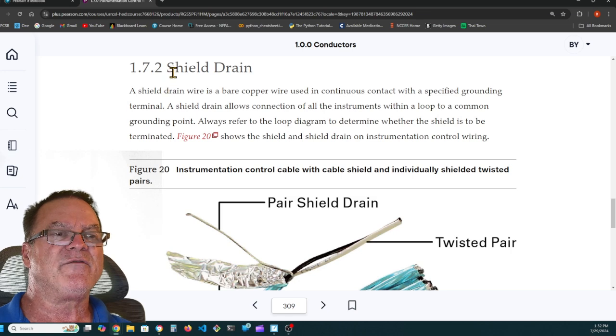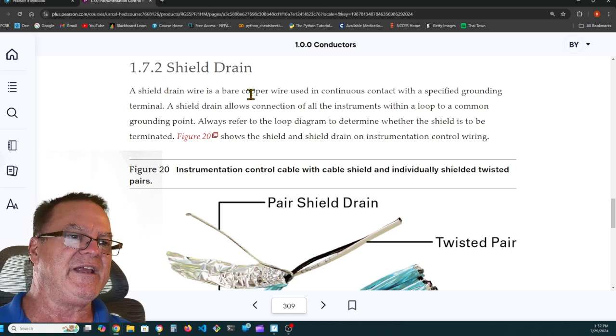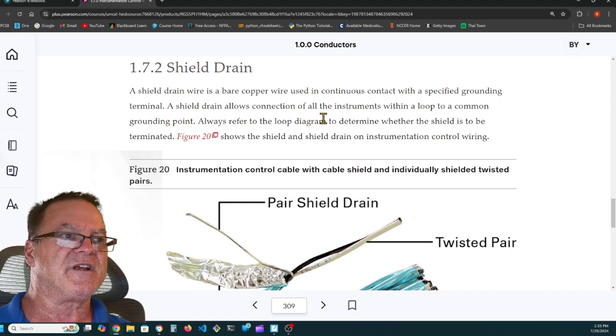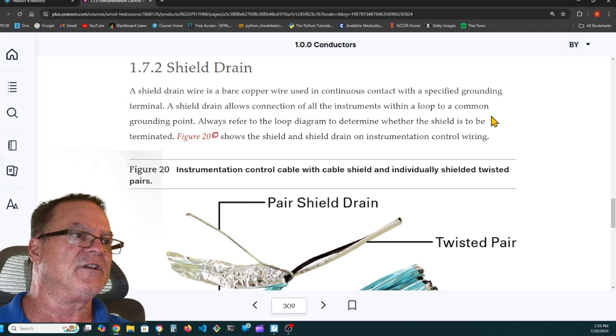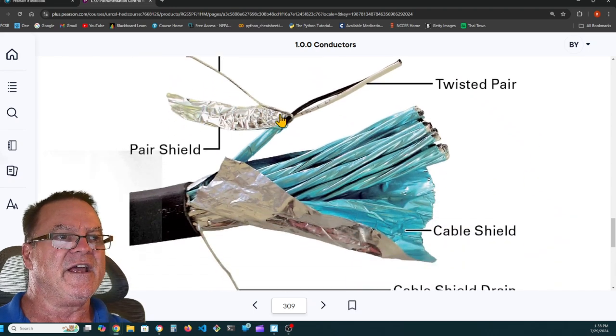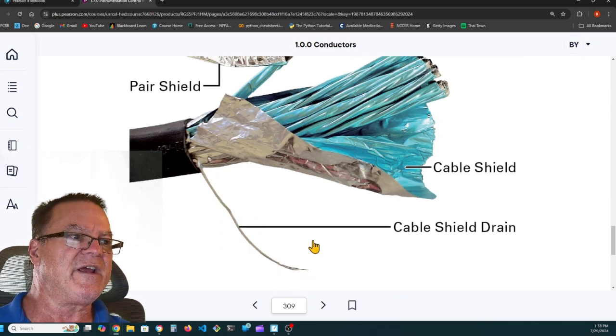All right. It's 1.7.2 shield drains. We only terminate the drain at one end. A shield drain wire is a bare copper wire used in continuous contact with a specified grounding terminal. A shield drain allows connection of all the instruments within a loop to a common grounding point. Always refer to the loop diagram to determine whether the shield is to be terminated. Figure 20 shows the shield and shield drain on instrumentation control wiring. Like I say, here's the shield and the shield drain. Here's the cable shield drain.